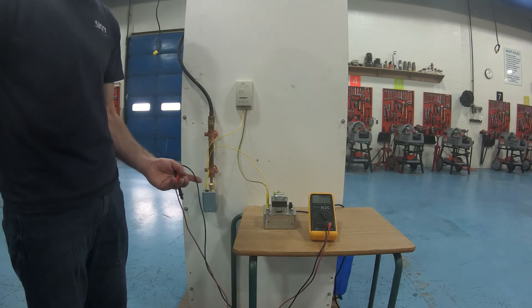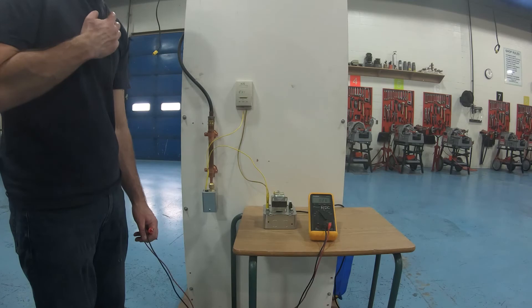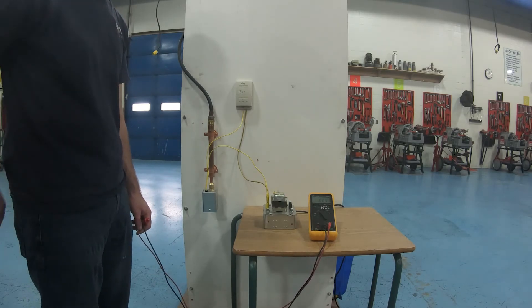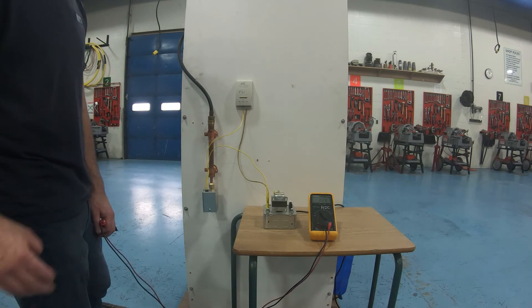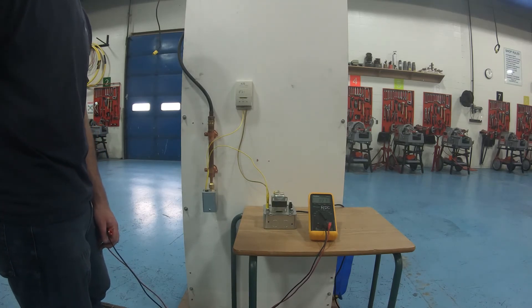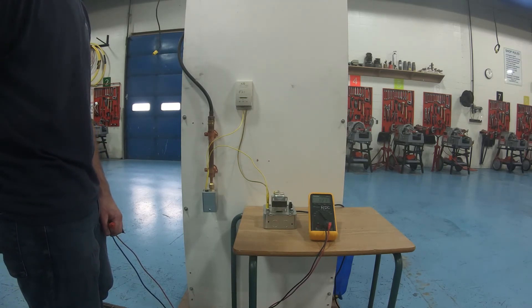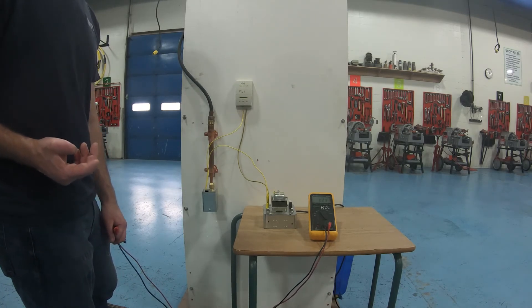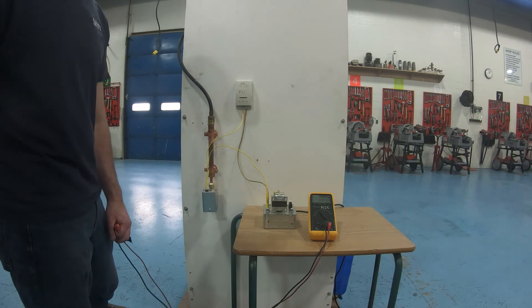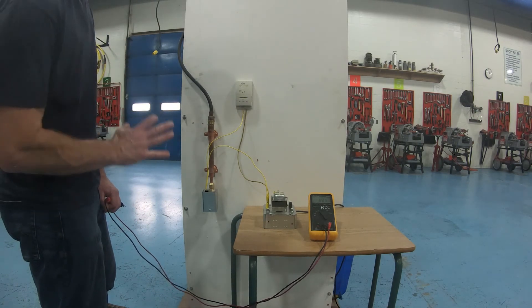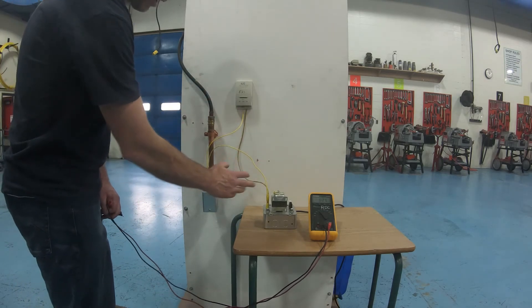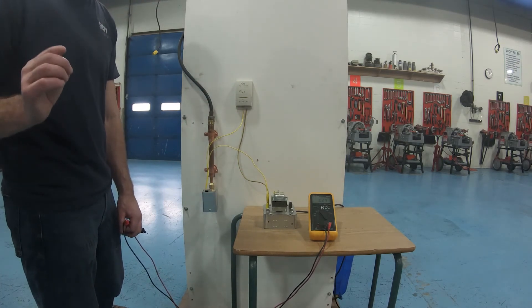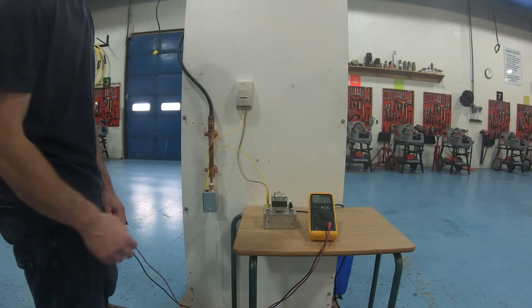Now the reason for this is when you're in an apartment building where you want something to fail in the safe position. So instead of having a no heat call in a big apartment building where a room could literally freeze solid, the complaint would be, my room is too hot, I've got the thermostat turned all the way down and my room is like 30 degrees Celsius, what's going on? Well, something is failing in the system here. It could be a power problem, it could be a zone valve problem, but it's failing open just like that.